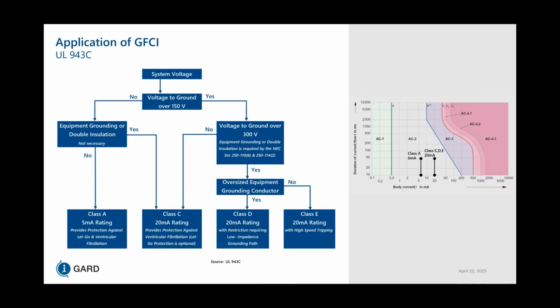Now, this decision tree is going to be the key point of how you decide which kind of class you are using. So starting from the top, we have our system voltage. If the voltage to ground is less than 150 volts and we have equipment grounding or double insulation, we can go with a Class C, 20 milliamp rated, which provides protection against ventricular fibrillation. If there's no equipment grounding or there's no double insulation, then you would go with the Class A, which is the 5 milliamp rating, and it provides protection against let go and ventricular fibrillation.